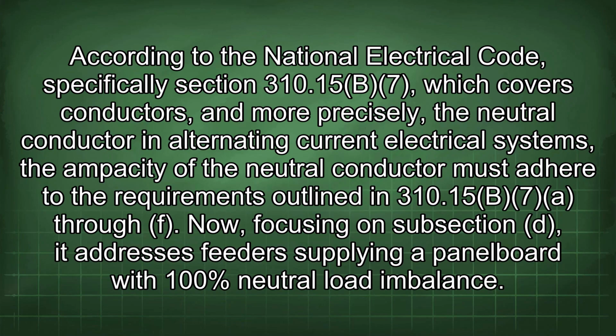According to the National Electrical Code, specifically Section 310.15(B)(7), which covers conductors, and more precisely the neutral conductor in alternating current electrical systems, the ampacity of the neutral conductor must adhere to the requirements outlined in 310.15(B)(7). Now, focusing on subsection D, it addresses feeders supplying a panel board with 100% neutral load imbalance.